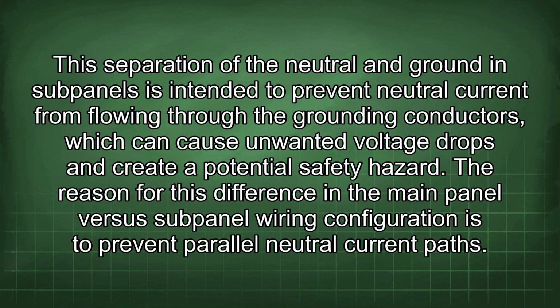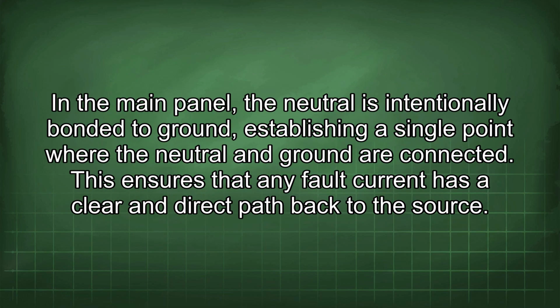This separation of the neutral and ground in subpanels is intended to prevent neutral current from flowing through the grounding conductors, which can cause unwanted voltage drops and create a potential safety hazard. The reason for this difference in the main panel versus subpanel wiring configuration is to prevent parallel neutral current paths. In the main panel, the neutral is intentionally bonded to ground, establishing a single point where the neutral and ground are connected. This ensures that any fault current has a clear and direct path back to the source.